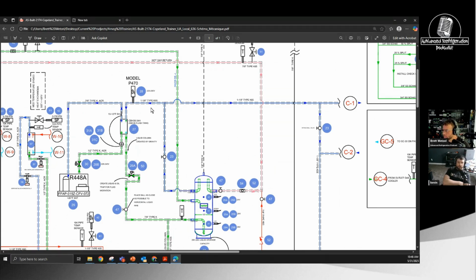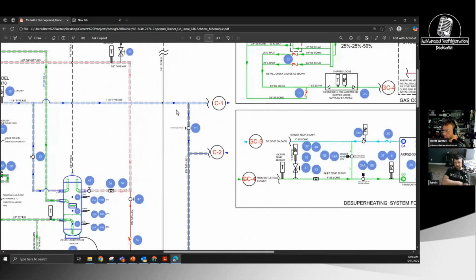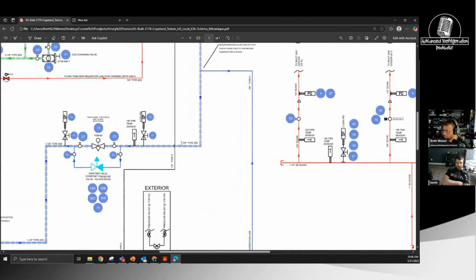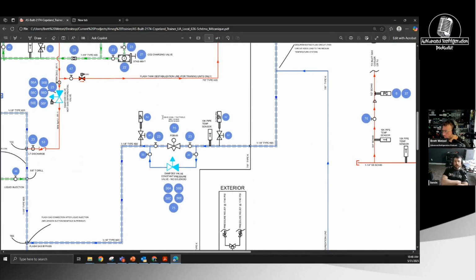Now this is where it gets a little - no, that's going to the heat exchanger for the backup unit. And then if you follow it all the way around, this is where it got pretty cool. So go down, right, it's there, going to your flash gas bypass valve. And then in parallel with this, they have a Danfoss constant pressure valve.